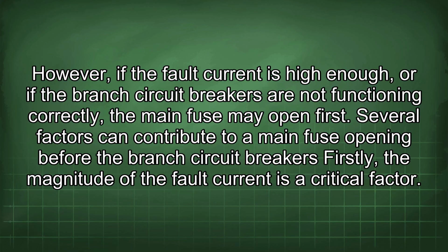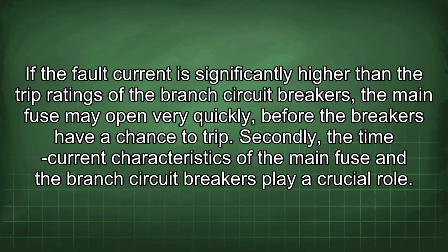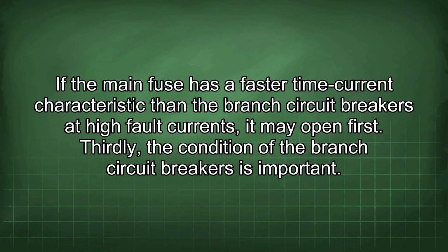Firstly, the magnitude of the fault current is a critical factor. If the fault current is significantly higher than the trip ratings of the branch circuit breakers, the main fuse may open very quickly before the breakers have a chance to trip. Secondly, the time current characteristics of the main fuse and the branch circuit breakers play a crucial role. If the main fuse has a faster time current characteristic than the branch circuit breakers at high fault currents, it may open first. Thirdly, the condition of the branch circuit breakers is important.